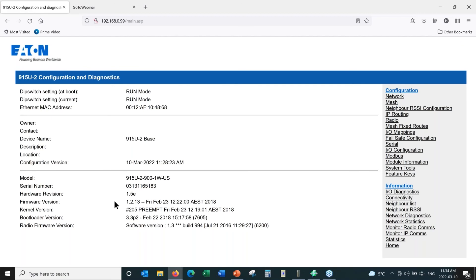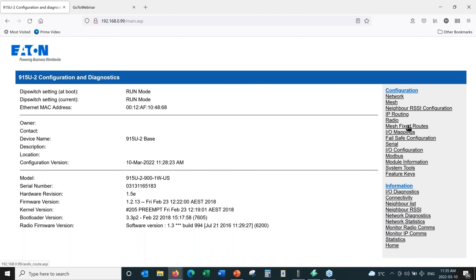Here is the web page diagnostics for these radios. The login page tells you the setup versus run mode dip switch status — we are currently in run mode. It tells you the name of the radio system, the serial number, and the firmware version. Those are the most important pieces. If the radio were in setup mode, the default IP address would be the one printed on the side label, and the radio firmware version would not be available because the radio module is powered off in setup mode. All the functions from the Windows-based software are duplicated here.